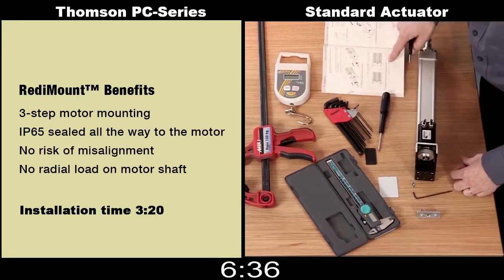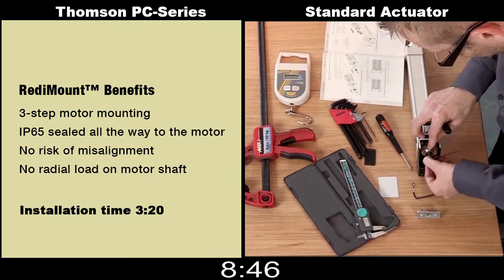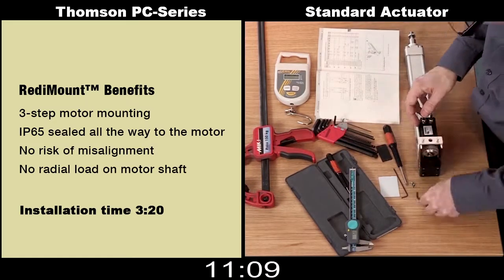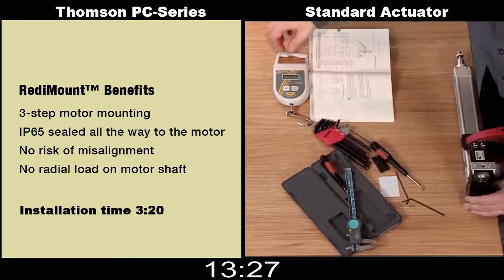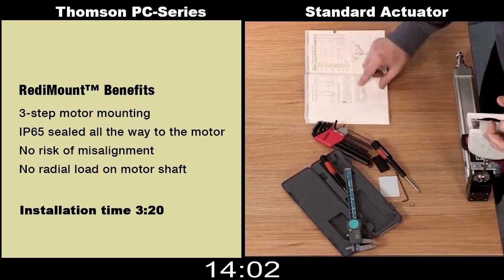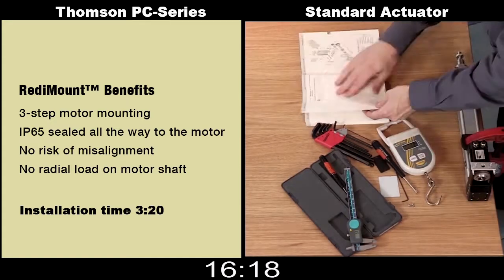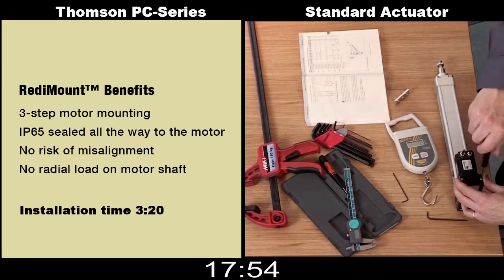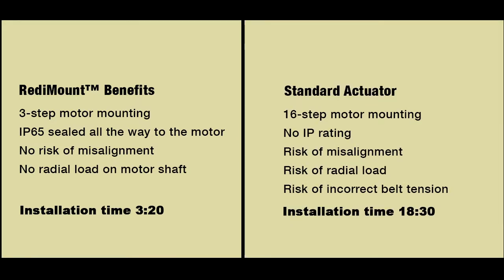While the assembly of the industry standard actuator continues, let's discuss some of the additional benefits of the PC series RediMount system. First, it comes designed with a dual or straddle mounted bearing system, eliminating any risk of misalignment and making sure that the shaft of the motor itself will not be subjected to any radial loads. This is important not only for noise but also to avoid shortened life of the motor. Furthermore, not only is the actuator itself IP65 rated, but also the PC series RediMount all the way to the motor, providing a robust piece of equipment for use in harsh environments where wash-down or cleaning is required.